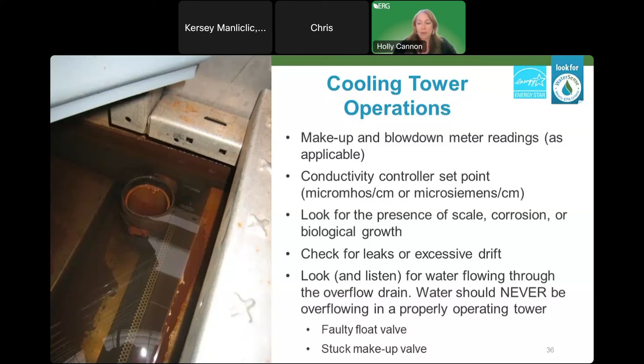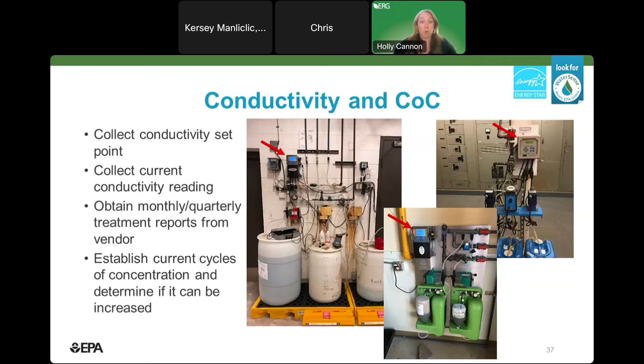Conductivity, like we talked about, is a measure of how efficiently your cooling tower is operating. The higher number of cycles of concentration is the greater efficiency. So the cycles are largely dependent on the incoming water quality and the water treatment that you have available. You want to check that conductivity controller, like we talked about, check the set point and the current meter reading. If they're vastly different, there may be something going on. You want to try to collect any water treatment reports. Oftentimes there'll be a water treatment vendor. They leave a report behind monthly or quarterly that will have some information on it about the tower, the type of maintenance they're doing, the water quality, and that can help you figure out the total water use of the tower.